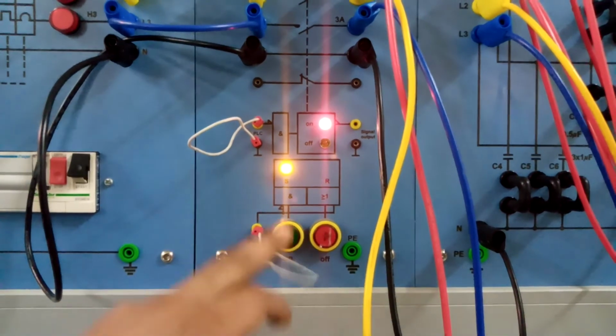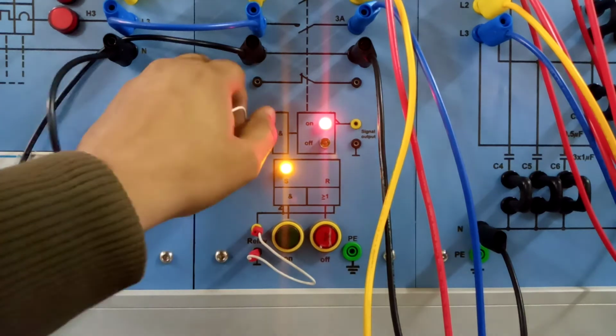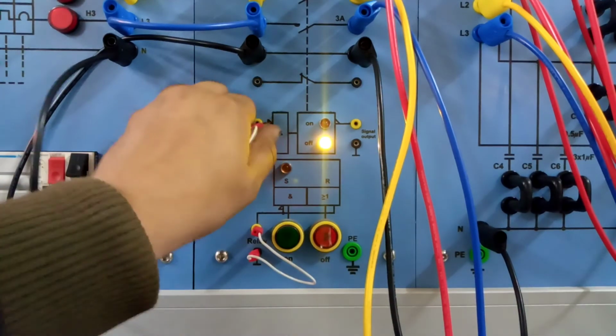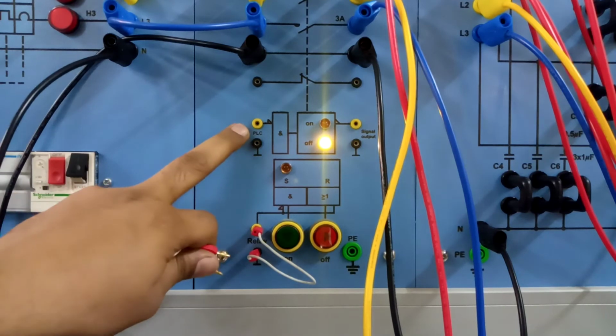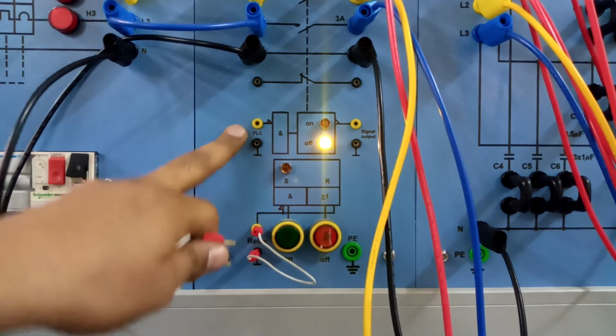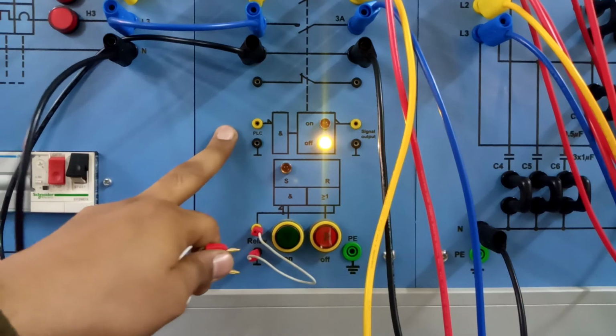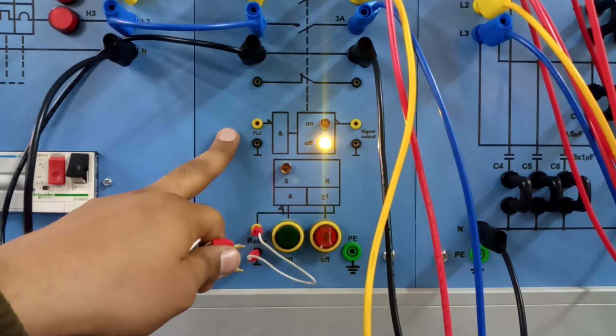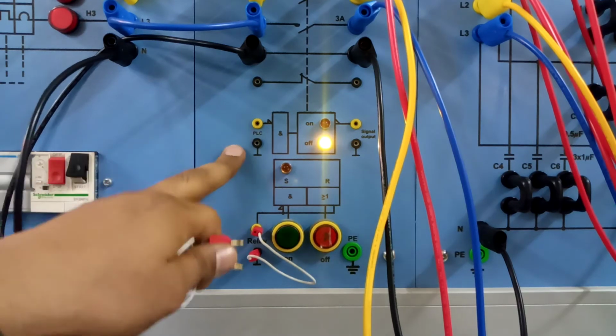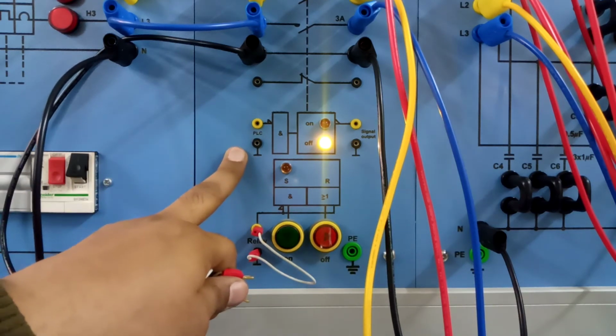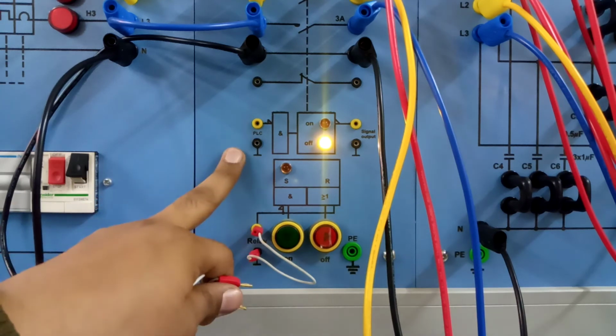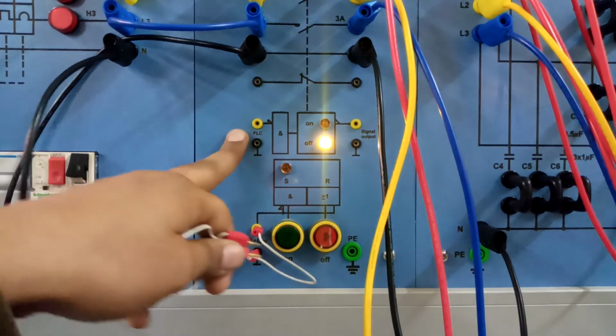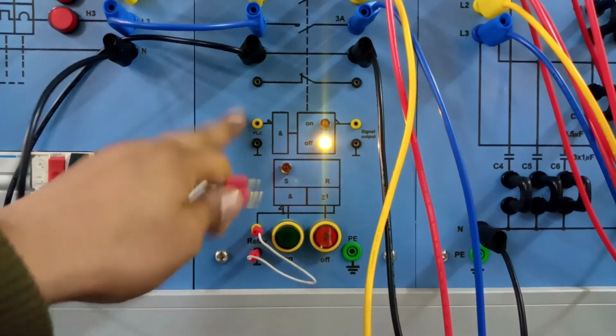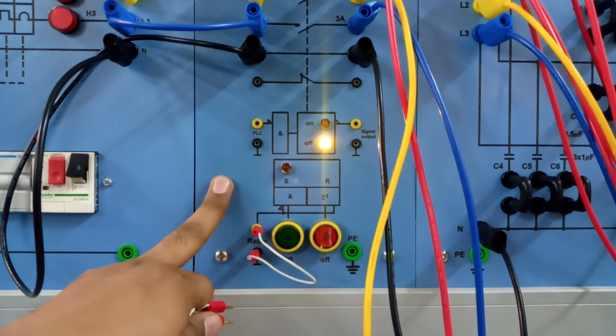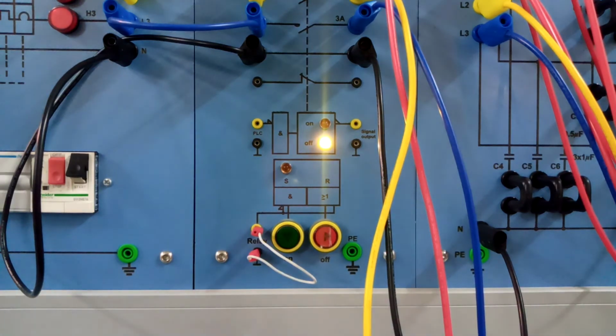Off, on. So now our target is to connect this, let me turn it off. We will connect this connection with our relay, and we will break, or discontinue this connection when there is a fault. When there is a fault, this connection will open, since this is a normally closed connection. So we will connect it as normally closed, and when there is a fault, this connection will open and our power circuit breaker will be turned off, or it will operate. Let's see how we can make the connections.